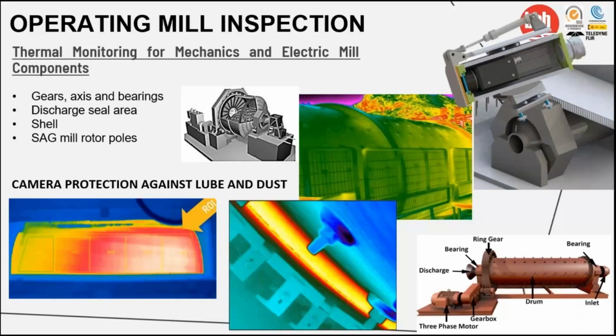We have high-speed cameras with which we can analyze each of the poles and determine if there are any temperature discontinuities in any of them and in which one specifically. In addition to this, we can also determine temperatures and detect thermal discontinuities in the pinion gear section. This is for both SAG mills and ball mills. As we can see in the image below, we precisely monitor the temperature along the mill shell and detect any thermal changes. If this occurs, we can promptly raise an alarm.